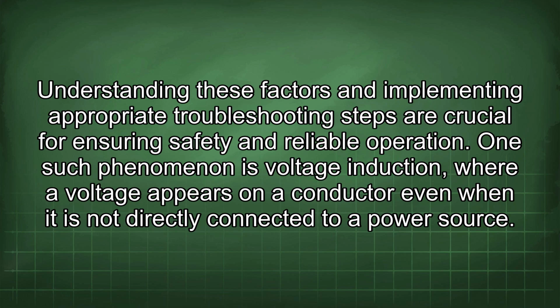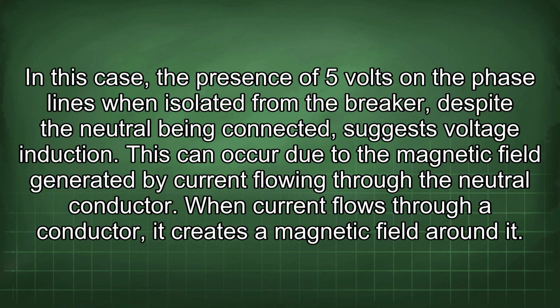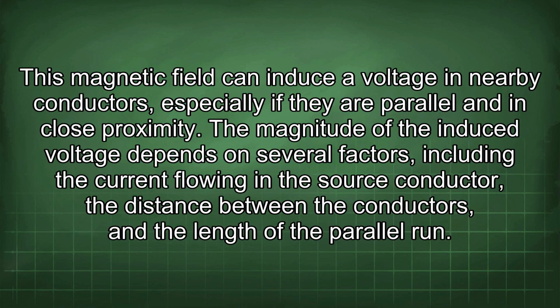One such phenomenon is voltage induction, where a voltage appears on a conductor even when it is not directly connected to a power source. In this case, the presence of 5 volts on the phase lines when isolated from the breaker, despite the neutral being connected, suggests voltage induction. This can occur due to the magnetic field generated by current flowing through the neutral conductor. When current flows through a conductor, it creates a magnetic field around it. This magnetic field can induce a voltage in nearby conductors, especially if they are parallel and in close proximity.